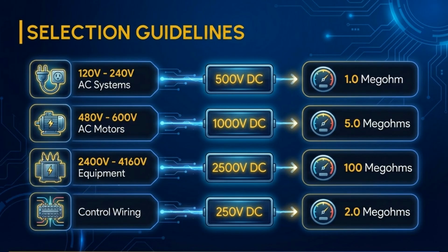For 120 to 240 volt AC systems, use 500 volts DC with a minimum of 1.0 Megohm. Higher voltage equipment requires correspondingly higher test voltages and minimum resistance values.